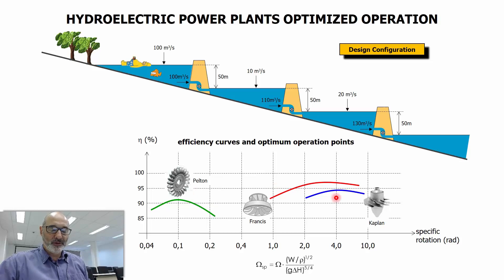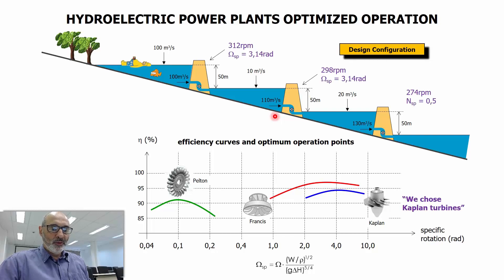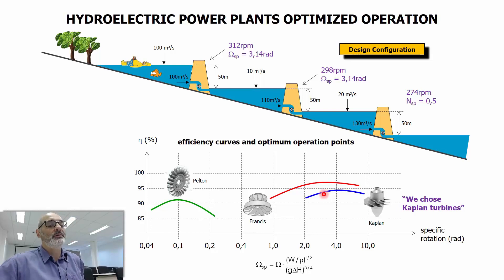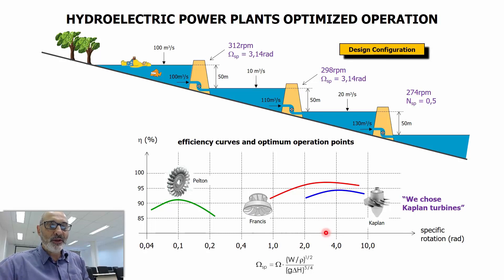When we calculate the specific rotations for our data — this height, this flow rate, and so on — we get values of 3.14 and 0.5. So we're going to choose a Kaplan turbine. 3.14 corresponds to approximately this point; we could choose Francis, but I'm choosing Kaplan because in the Tietê River they are all Kaplan turbines, to remain close to our local reality here in São Paulo.